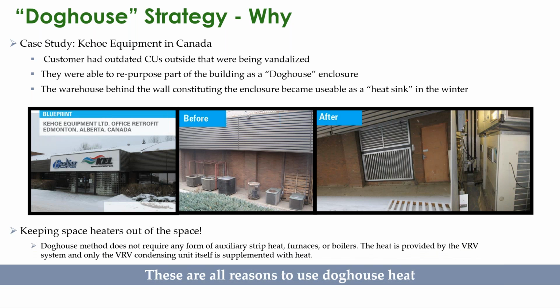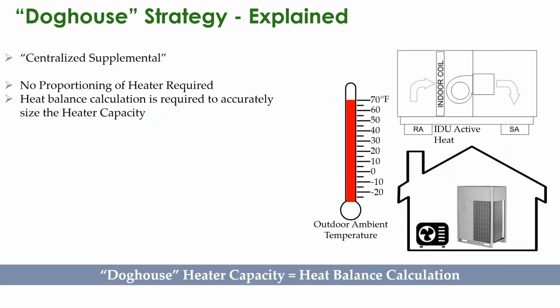This keeps the space heaters out of the space. So if you're in a wall hung or ceiling cassette type situation, and somebody does not want to see baseboard heaters or Cadet wall heaters or small unit heaters, this gives you that option because you're only keeping the supplement going for the outdoor unit. This is also referred to as centralized supplemental. You don't have to proportion the heat. You don't have the added cost of each individual heater at the indoors.